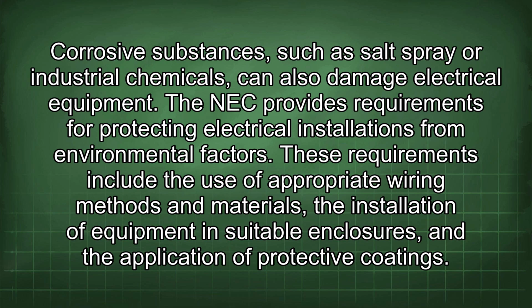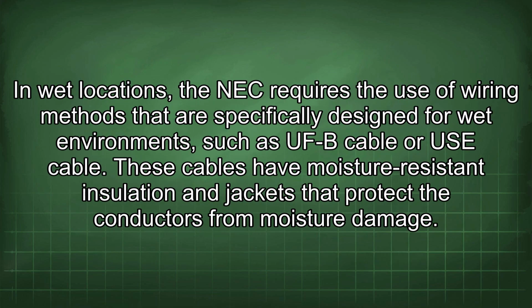application of protective coatings. In wet locations, the NEC requires the use of wiring methods that are specifically designed for wet environments, such as UF-B cable or USE cable. These cables have moisture-resistant insulation and jackets that protect the conductors from moisture damage.